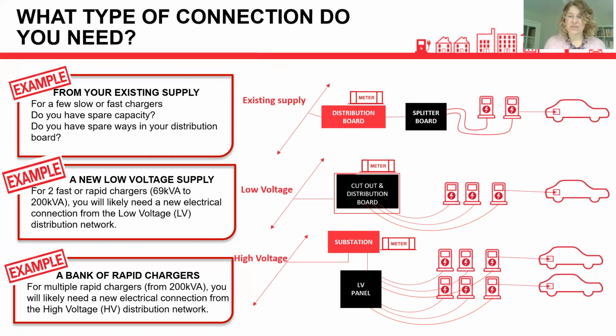If you're looking to install more chargers, or for example a couple of rapid chargers around 50 kilowatts, and you don't have the existing spare capacity, anything up to say 150 to 200 kVA, you're likely to be granted a new connection from the low voltage network.